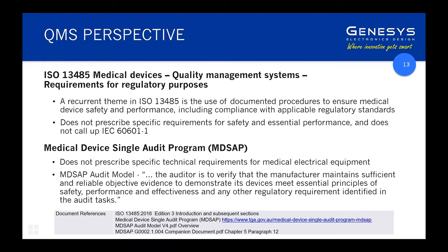MDSAP is kind of 13485 on steroids, applying to specific jurisdictions — Australia, Canada, Brazil, and the US — where you can have a single process to ensure compliance. It's not mandatory, and the jury's a little out on whether it's worth the effort. We've heard from quality consultants that it's a lot of work. Looking at major jurisdictions — TGA, European Commission, FDA, and Health Canada — you'll find globally harmonized standards closely aligned with 60601-1, with only minor regional differences such as mains voltage, frequency, and multilingual documentation requirements.